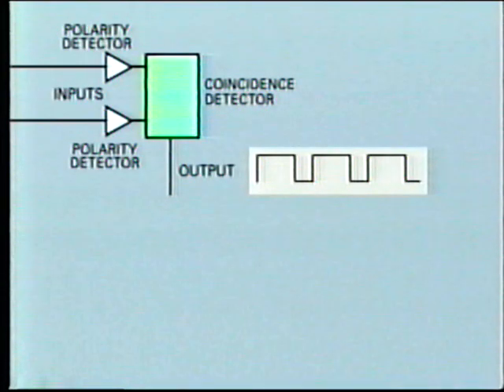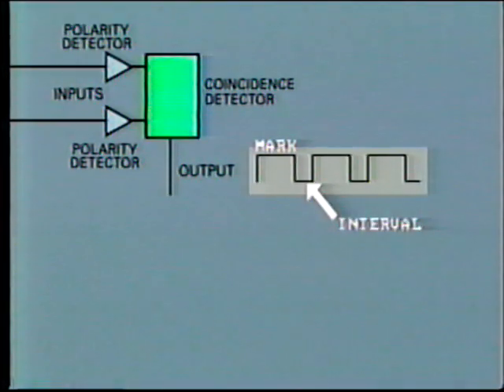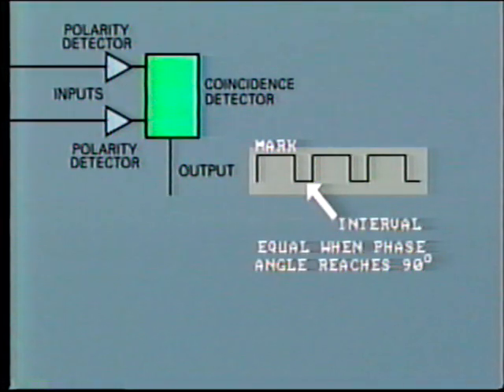Actually, measuring the mean DC voltage is too slow for some protection devices, particularly directional or mho relays, where it's extremely important to detect the condition of 90 degrees phase angle difference. A faster way of achieving this is to measure and compare the mark and interval times. These are equal when the phase angle reaches 90 degrees.